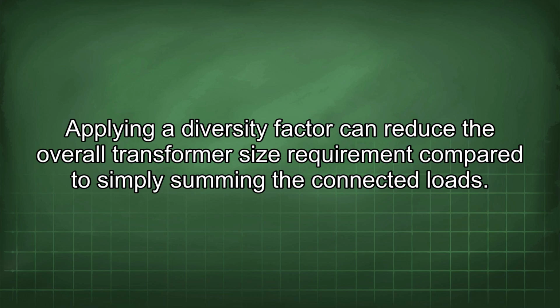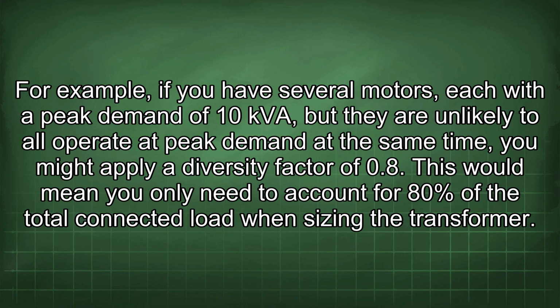Applying a diversity factor can reduce the overall transformer size requirement compared to simply summing the connected loads. For example, if you have several motors, each with a peak demand of 10 kVA, but they are unlikely to all operate at peak demand at the same time, you might apply a diversity factor of 0.8. This would mean you only need to account for 80% of the total connected load when sizing the transformer.